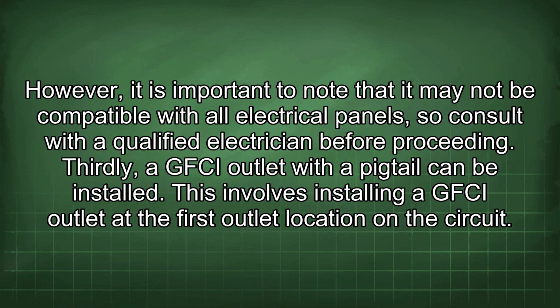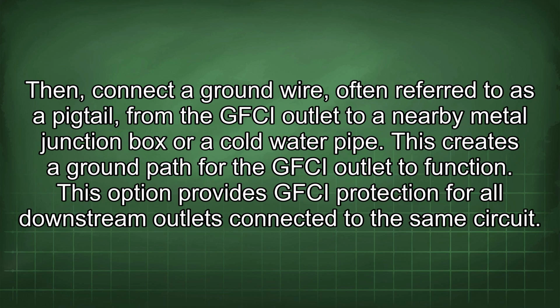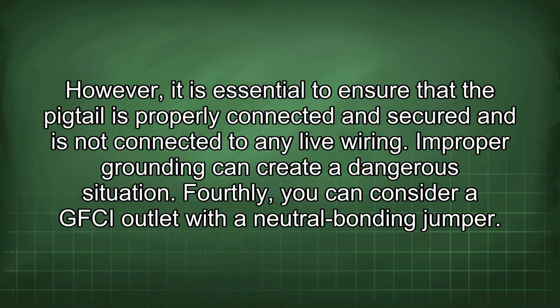Thirdly, a GFCI outlet with a pigtail can be installed. This involves installing a GFCI outlet at the first outlet location in the circuit. Then connect a ground wire, often referred to as a pigtail, from the GFCI outlet to a nearby metal junction box or a cold water pipe. This creates a ground path for the GFCI outlet to function. This option provides GFCI protection for all downstream outlets connected to the same circuit. However, it is essential to ensure that the pigtail is properly connected and secured and is not connected to any live wiring. Improper grounding can create a dangerous situation.